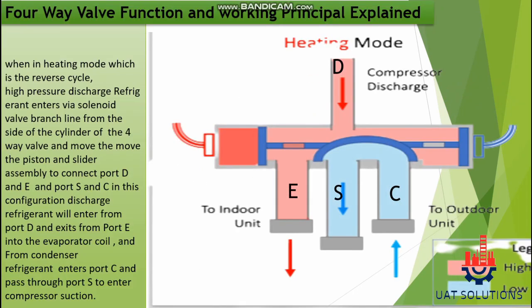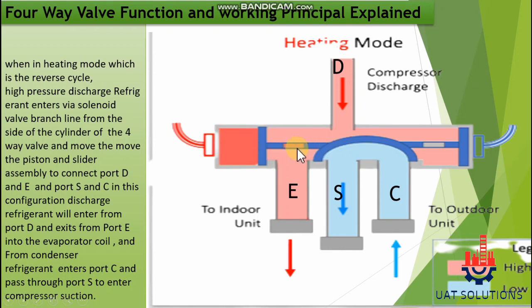When in heating mode, which is the reverse cycle, high pressure discharge refrigerant enters via the solenoid valve branch line from the side of the cylinder of the four-way valve, and moves the piston and slider assembly to connect port D and E, and also connects port S and C.